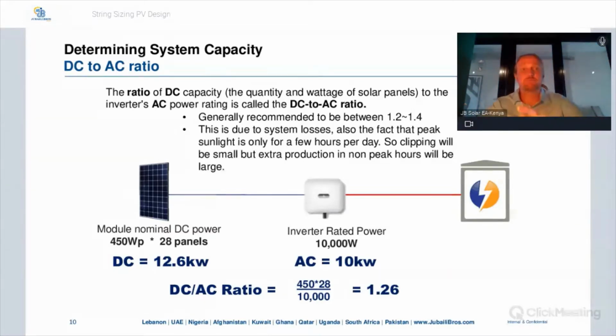So we use 1.3. The reason for this is there's system losses, there's DC losses, so not all of the DC capacity will reach the inverter. However, also, this is for extra production in the early mornings and the afternoons. So during the peak hours of sunlight, there may be some clipping with the 1.3 DC to AC ratio, because the DC will be more than the AC can handle. But that clipping will be minimal because the peak hours of sunlight do not happen very often and do not happen very long.